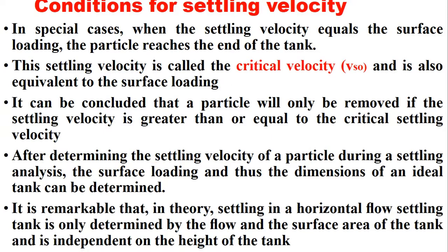process during water treatment. So it is remarkable that in theory, settling in a horizontal flow settling tank is only determined by the flow and the surface area of the tank, and is independent of the height of the tank.